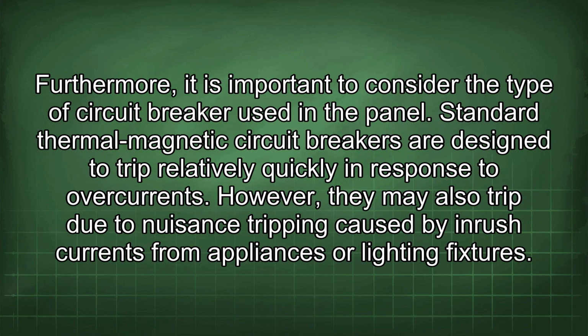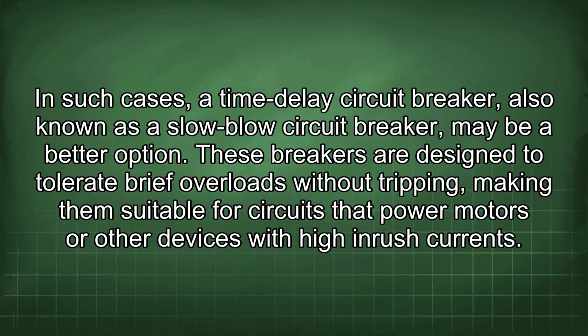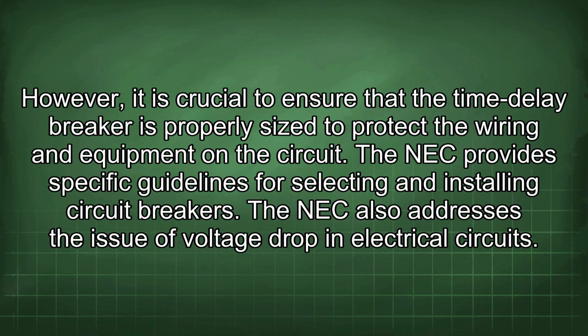Furthermore, it is important to consider the type of circuit breaker used in the panel. Standard thermal magnetic circuit breakers are designed to trip relatively quickly in response to overcurrents. However, they may also trip due to nuisance tripping caused by inrush currents from appliances or lighting fixtures. In such cases, a time delay circuit breaker, also known as a slow blow circuit breaker, may be a better option. These breakers are designed to tolerate brief overloads without tripping, making them suitable for circuits that power motors or other devices with high inrush currents. However, it is crucial to ensure that the time delay breaker is properly sized to protect the wiring and equipment on the circuit. The NEC provides specific guidelines for selecting and installing circuit breakers.